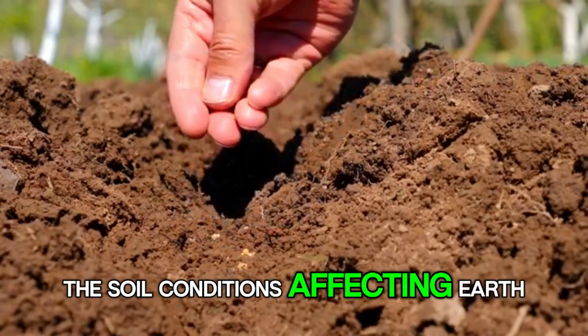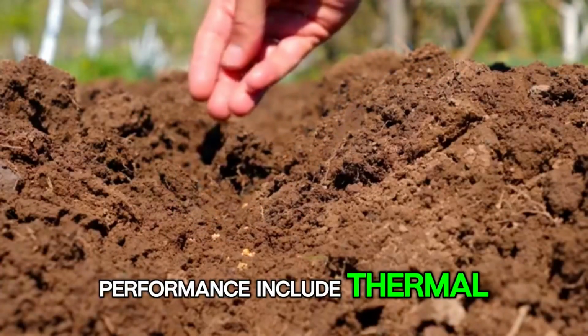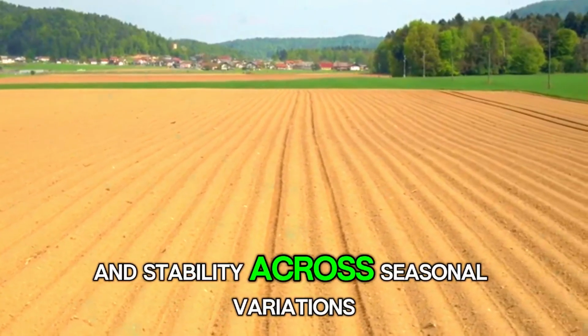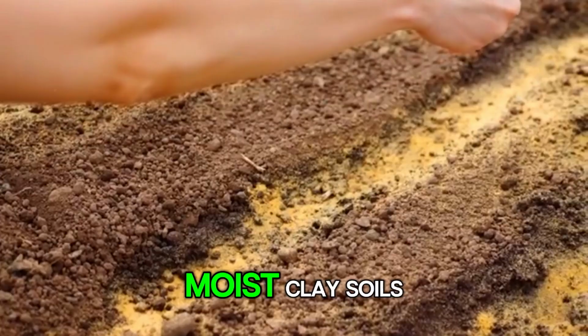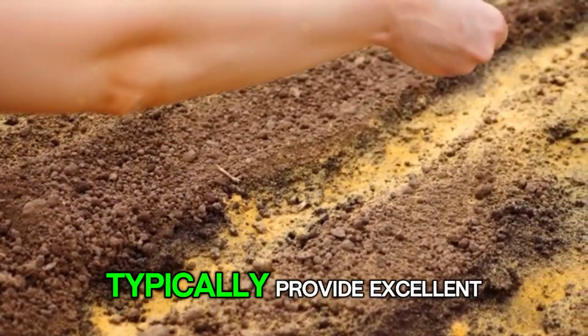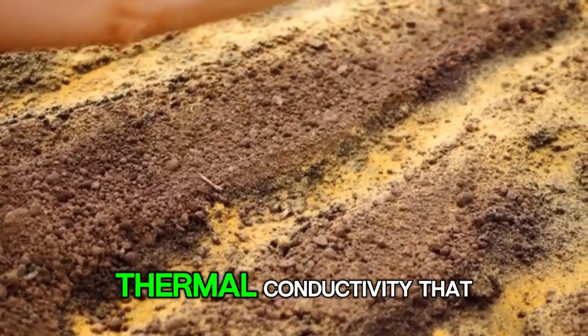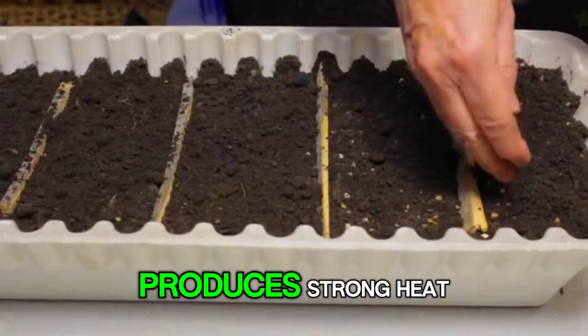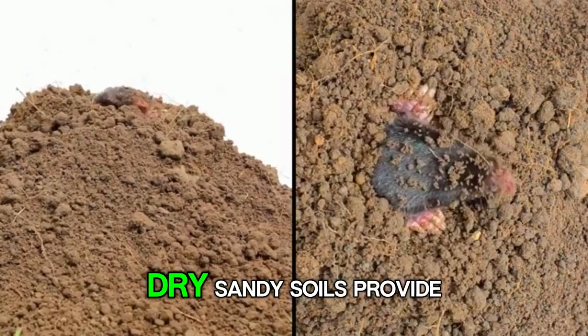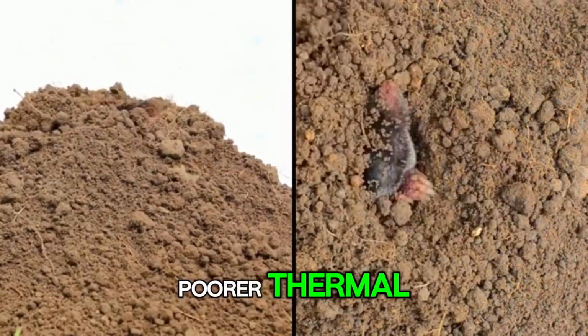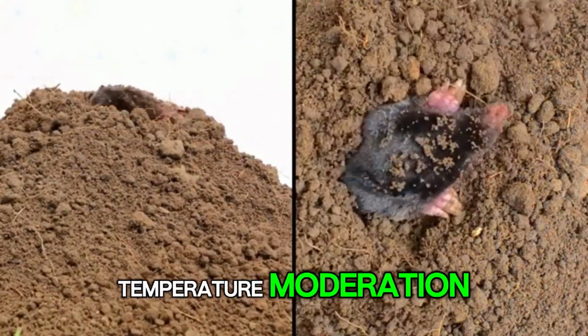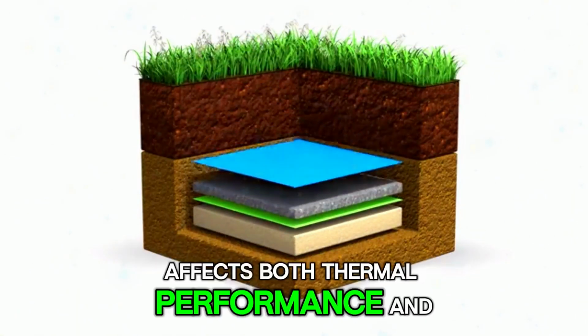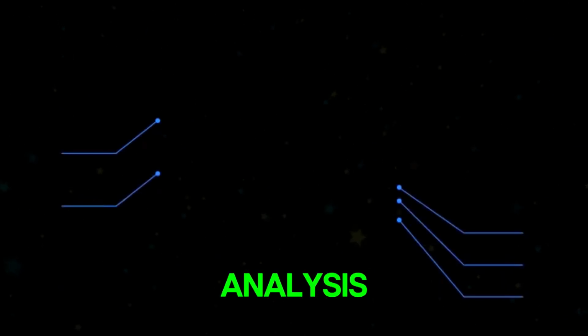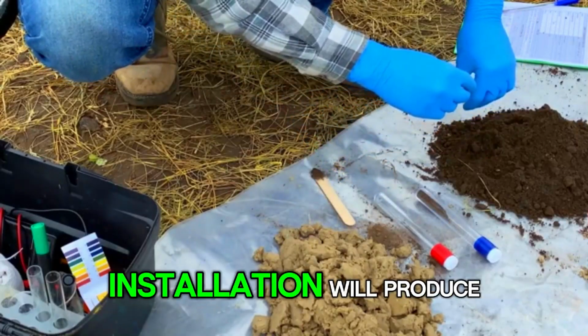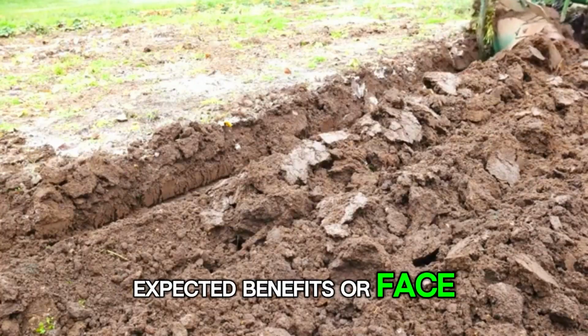The soil conditions affecting earth tube performance include thermal conductivity, moisture content, density, and stability across seasonal variations. Moist clay soils typically provide excellent thermal conductivity that produces strong heat transfer between pipe air and surrounding soil. Dry, sandy soils provide poorer thermal conductivity that reduces temperature moderation. Groundwater presence affects both thermal performance and installation feasibility. Proper site assessment includes soil analysis that determines whether earth tube installation will produce expected benefits or face performance challenges from unsuitable conditions.